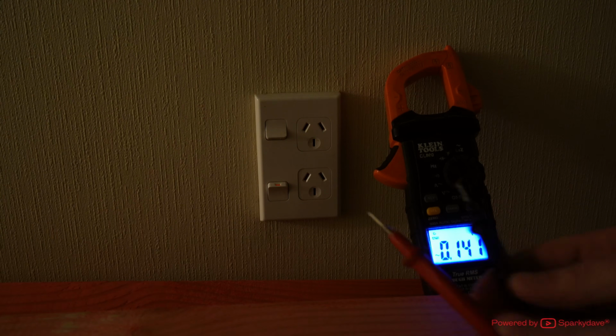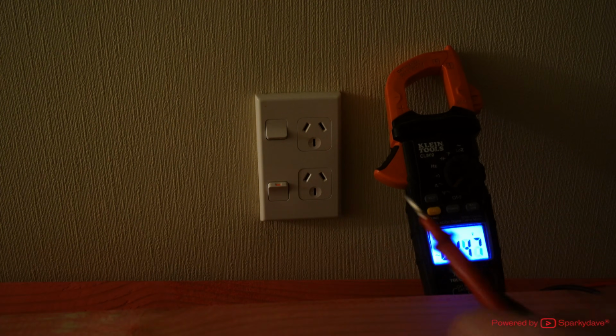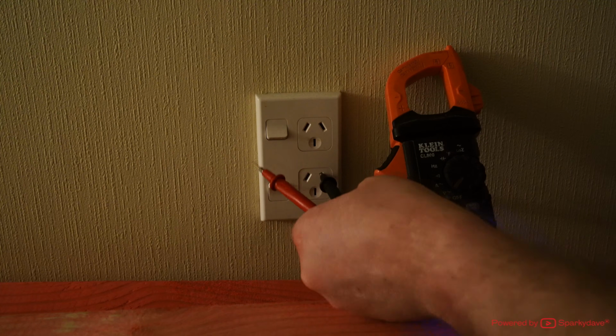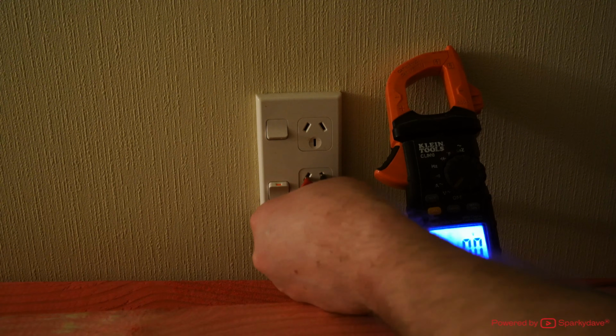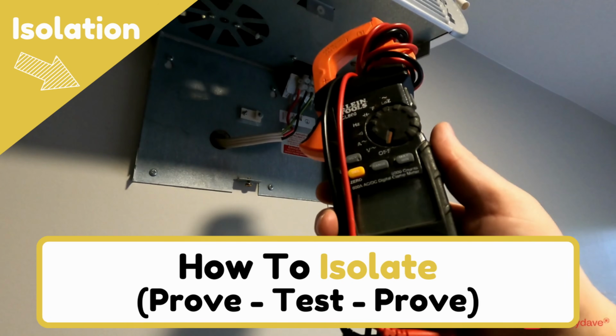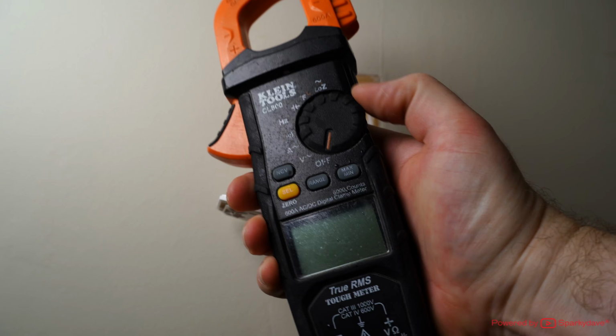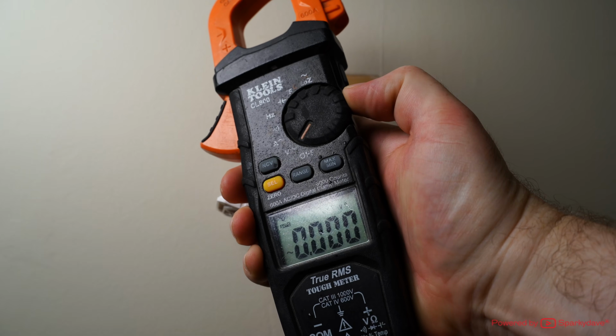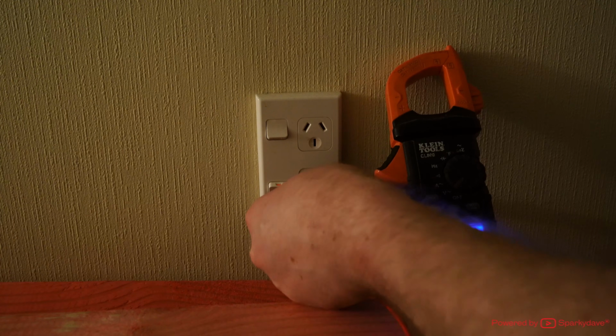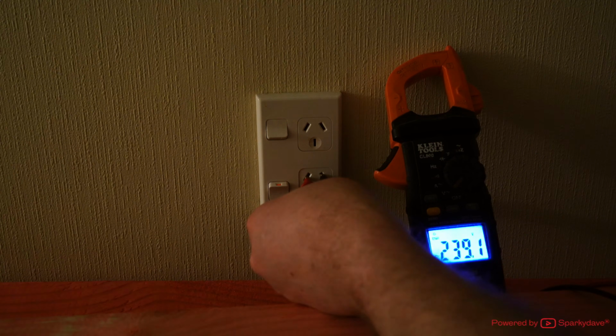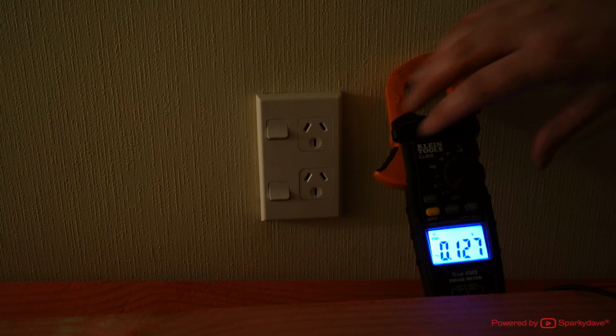Before and after testing an isolated circuit, the multimeter should test a known live circuit to ensure it reads voltage correctly. This is known as the prove-test-prove method. Switch the multimeter to voltage AC and use a nearby known live power source, such as a power point, to ensure the meter can read 230 volts.